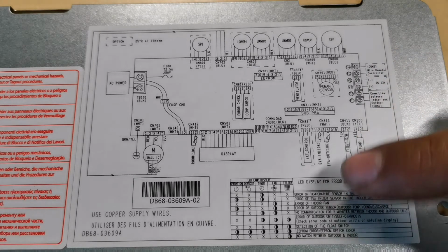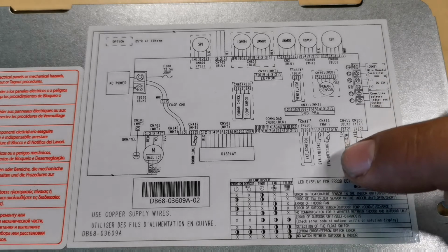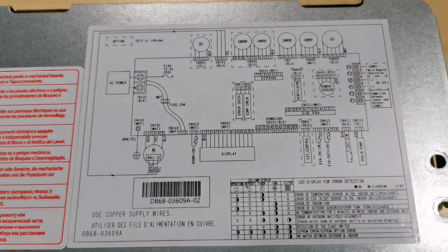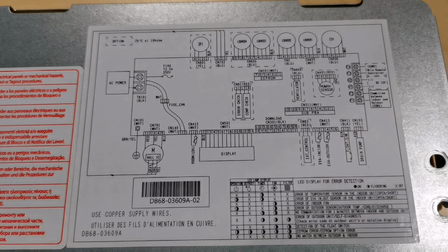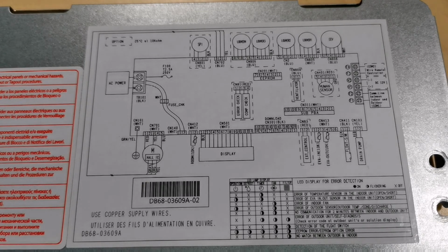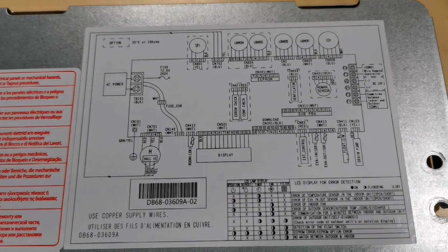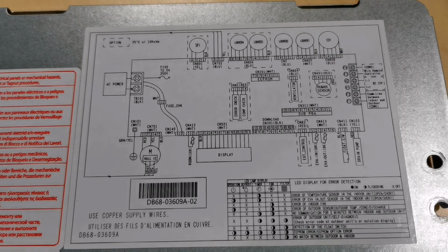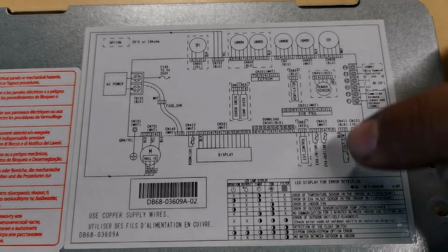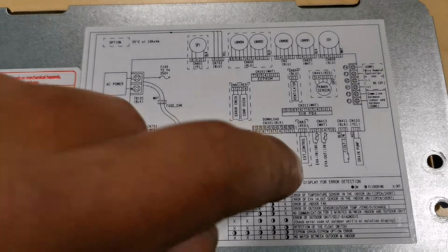Every resistor has temperature tolerances, but that 10K would obviously be at a fixed temperature, so please make sure that you guys, when you test sensors, have a look at your ambient and have a look at the chart, what the manufacturer says that sensor value needs to be at that respective temperature. So at 10 degrees your sensor value will be completely different to 25 degrees. So alright, we'll have a look and check.